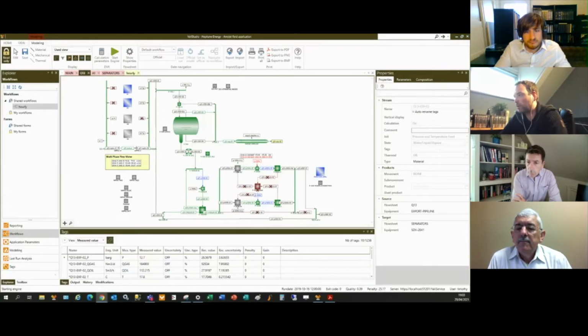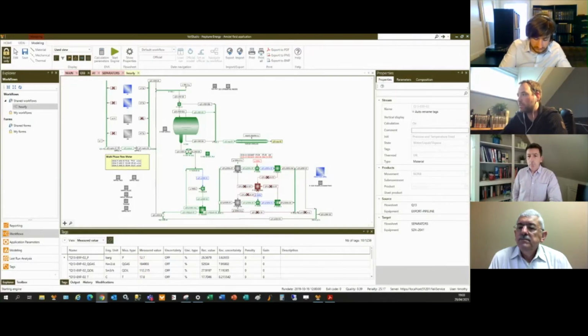The penalty is coming directly from this assumption that you know what the uncertainty of the initial measurement is. So in a sense, that's also, I would say, a bit of a fragile part of DVR, especially when you look at upstream and you have, for instance, multi-phase meters. Then, of course, you have the vendor spec, but you can also have meters that are performing in a region where they are not that comfortable. It also depends on if you look at oil flow or gas flow. So to get this a priori uncertainty, that's kind of a big challenge.